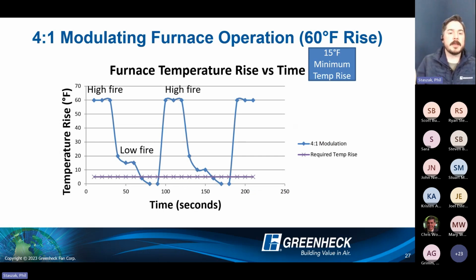Furnaces fire on with an indirect gas fired heater. They fire in high fire, then they modulate down to their lowest firing rate. So here we're on in high fire, and it modulates down. For our set point, we only need a 5 degree temperature rise to achieve whatever our leaving air temperature is. Well, since 15 degrees is our minimum, it's firing at low fire. It can't do anything else but shut down. Then it shuts down and brings in whatever outside air has to offer. There's a cool off period required, and then we're below set point. So we fire back on in high fire and then it's just a vicious cycle. The killer of all equipment is obviously furnace cycling, equipment cycling. Anytime you can just energize a relay or energize a unit and maintain, it's always going to be an advantage.